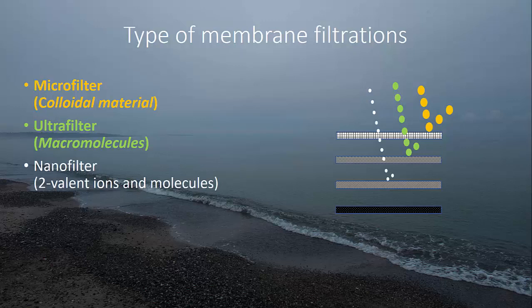With nanofilters we go down to very, very small openings in the membrane. A nanofilter can remove divalent ions and molecules such as calcium (2+) and magnesium, so nanofilters can also be used to soften water. Nanofilters are found in groundwater treatment and freshwater treatment, especially for removing color from lakes. Last, we come to reverse osmosis, which can remove chlorides and sodium salts. For drinking water or sewage treatment the three major membrane types are ultrafilters, nanofilters, and reverse osmosis. And what always passes through the membrane? The water — that is what we want to clean.